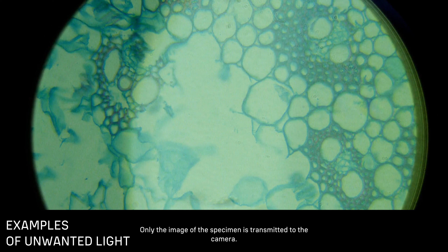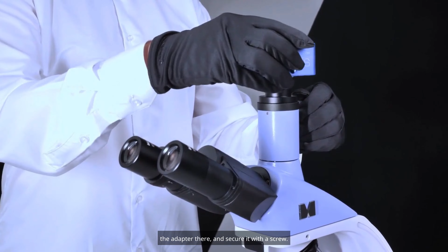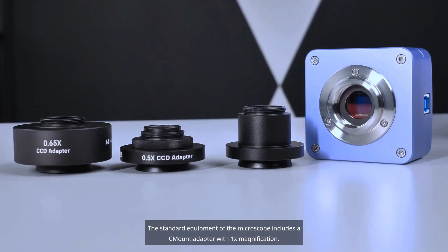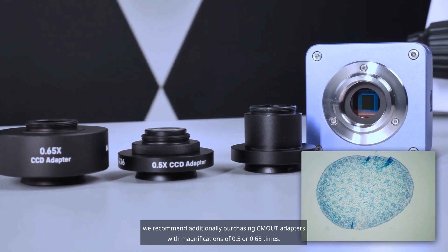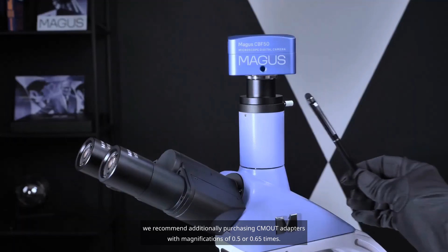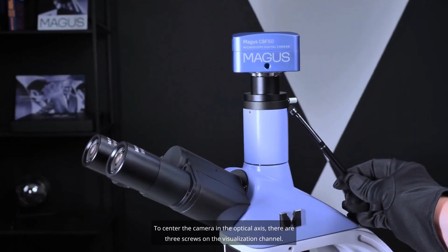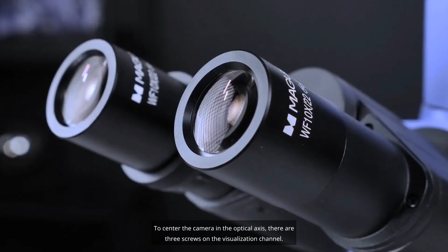To install the camera, we perform the following actions. We connect the camera with the C-mount adapter, remove the dust cover from the visualization channel, install the adapter there, and secure it with a screw. The standard equipment of the microscope includes a C-mount adapter with 1x magnification. A camera with a small sensor on a single adapter will provide too small a field of view. So for such cameras, we recommend additionally purchasing C-mount adapters with magnifications of 0.5 or 0.65 times. To center the camera in the optical axis, there are 3 screws on the visualization channel.